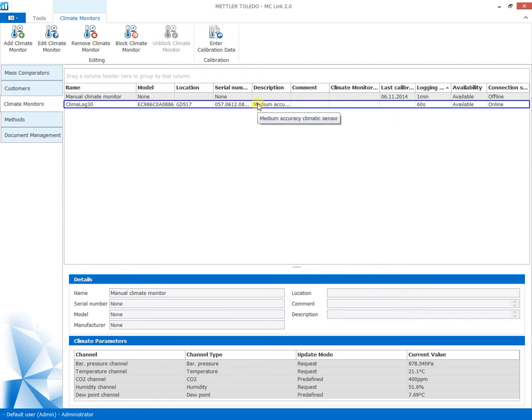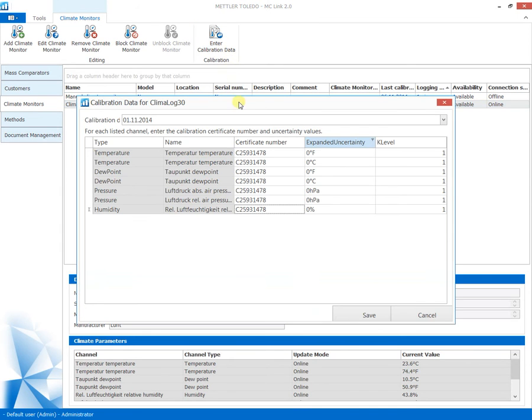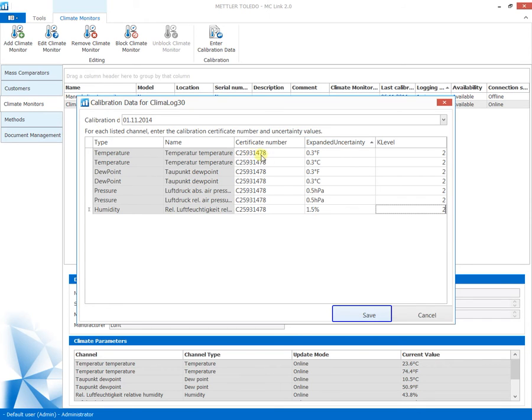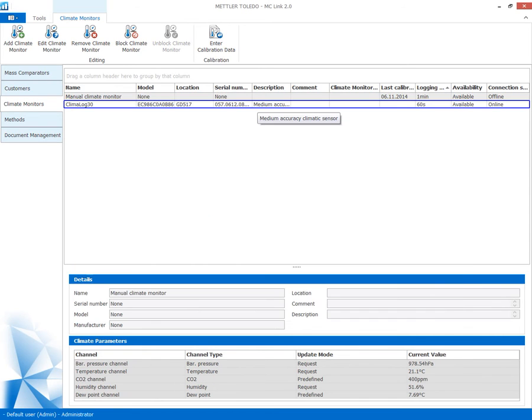Now the devices are connected to the system. To enable the full capability for the uncertainty calculations, the calibration data needs to be entered. Enter the certificate number from the calibration certificate and the expanded uncertainty of each channel and the corresponding coverage factor. By saving this data, the climatic sensor is ready to be used for mass calibration.